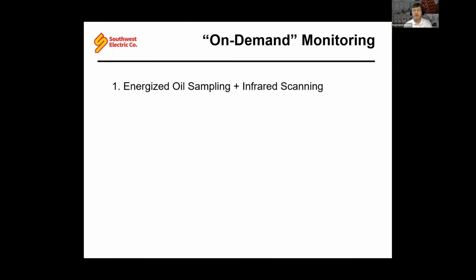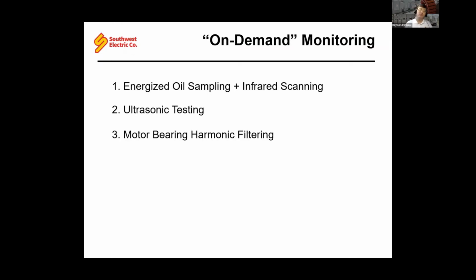One is obviously energized oil sampling. Oil sampling has been around for a long time, but energized oil sampling, there are many people who don't have this still. And this is something we want to introduce, coupled with infrared scanning. Also ultrasonic testing, and we'll get into what that means. And then also some motor bearing harmonic filtering. These things will end up saving a lot of headache and provide extended life for your equipment.